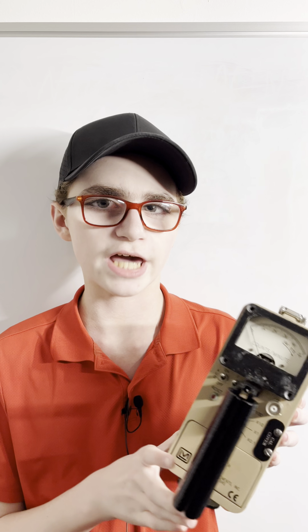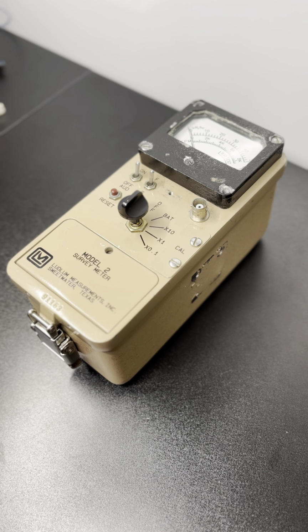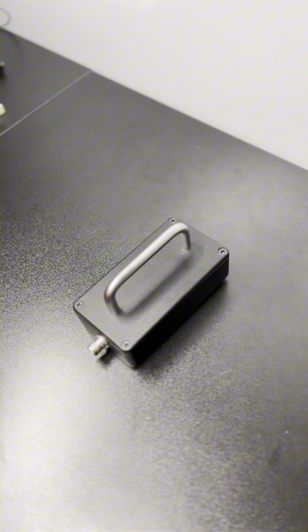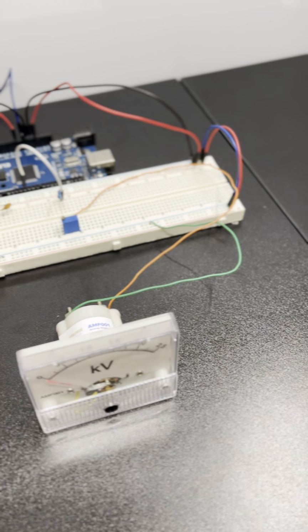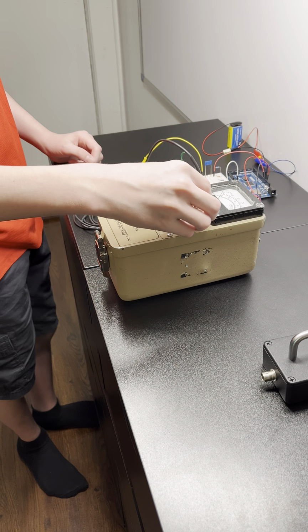Want to learn how vintage Geiger counters are calibrated? You do? Okay, perfect. Let's calibrate this Ludlum Model 2. The first thing we do is select a probe, and then lock down the proper operating voltage for it. I grab an ultra-high impedance voltmeter with a 1 gigaohm input impedance and connect it to the measuring device.